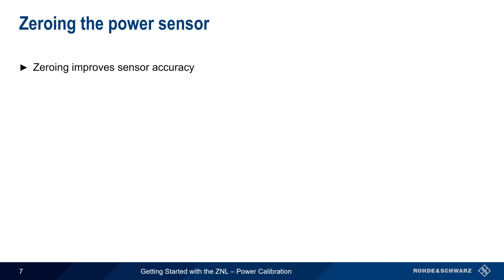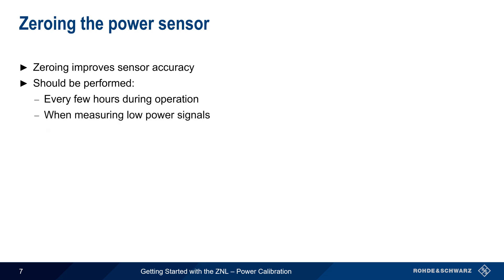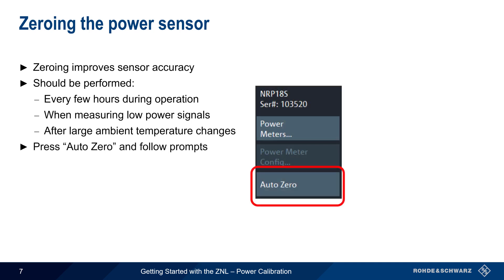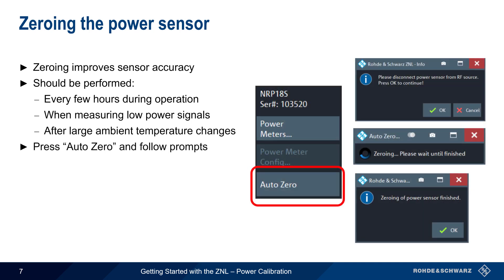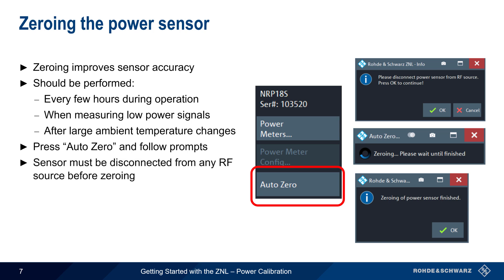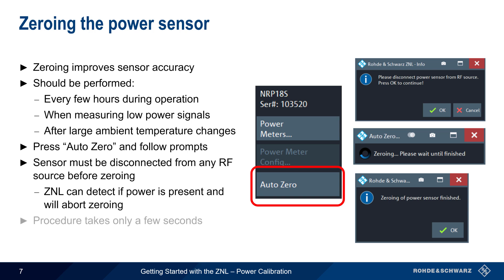Zeroing the selected power sensor will improve sensor accuracy. Zeroing should be performed every few hours under normal conditions, but it's particularly important when measuring lower power signals or after a large change in ambient temperature. The sensor must be disconnected from any source of RF power during zeroing, but in most cases the ZNL will automatically abort the test if it detects that power is present at the sensor. The entire zeroing process typically takes only a few seconds.